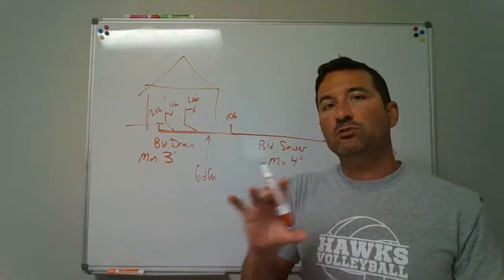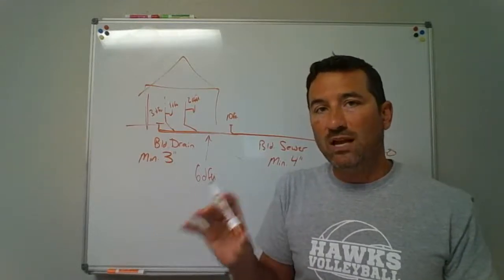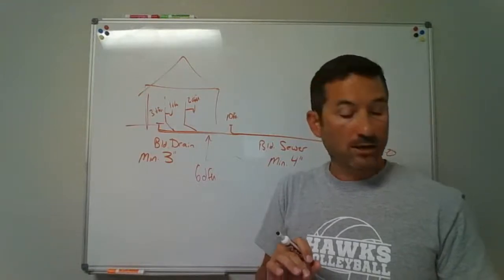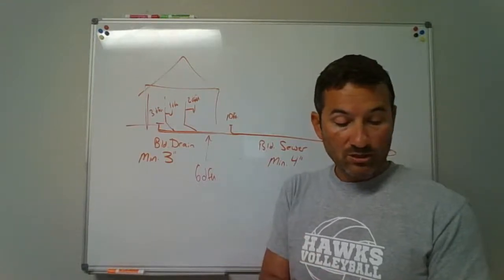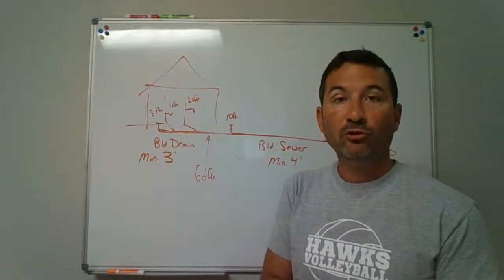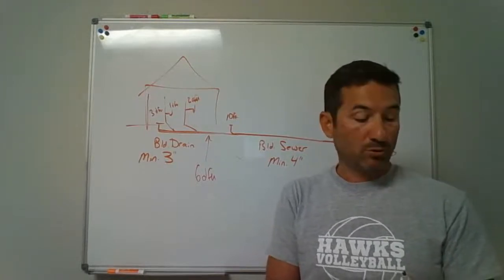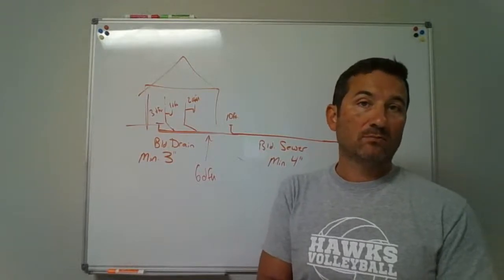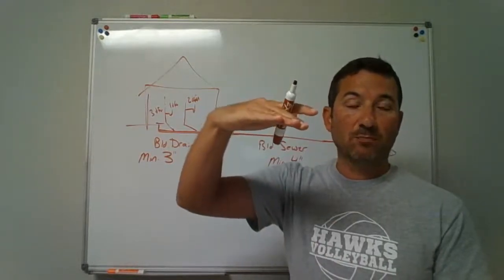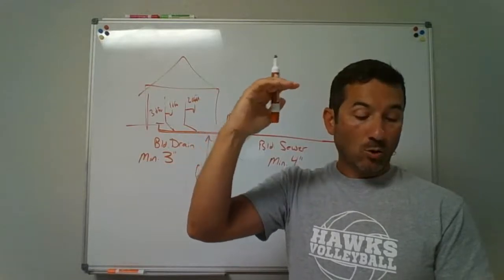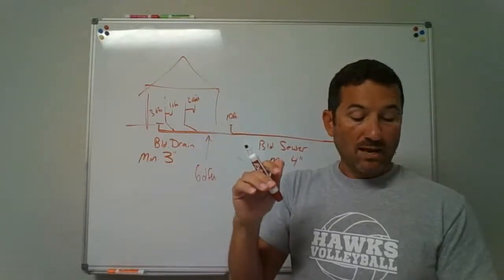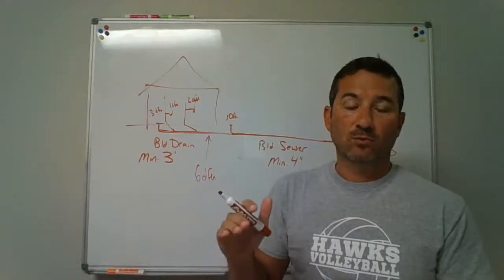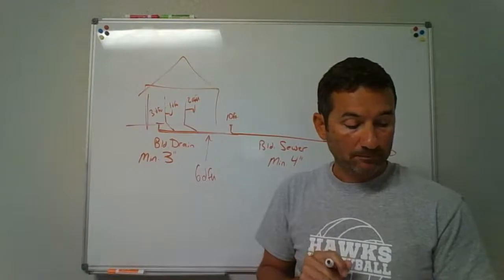If I ran those 3-inch drains at their minimum slope, which is an eighth of an inch per foot, how many DFUs can I put on that 3-inch drain? You look at 3-inch and go over to the eighth inch and it says 36 DFUs. Now I can get a few more DFUs out of it if I put the pitch a little bit steeper, a quarter of an inch per foot, then I can go up to 42 DFUs on that exact same drain.